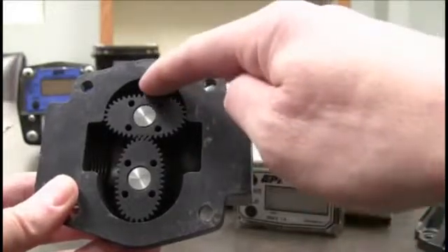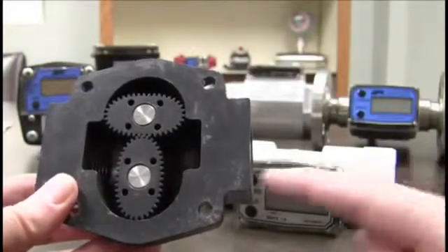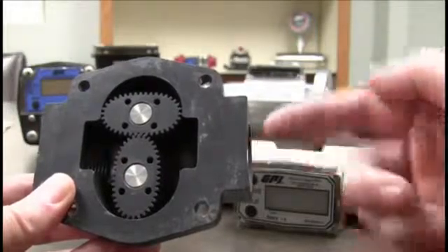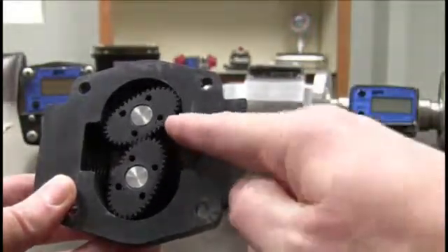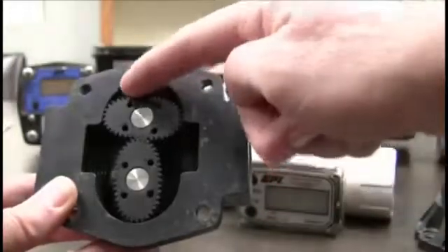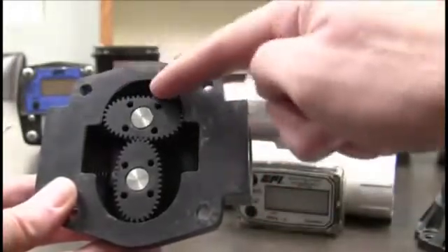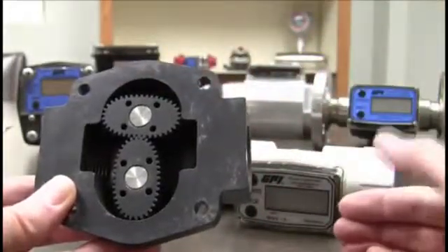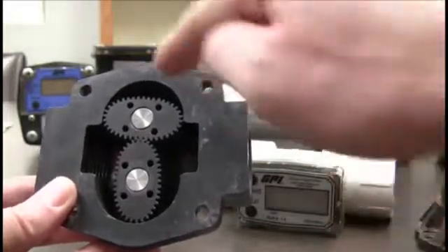And you see this little chamber here. That is where the fluid goes through. So if you have your fluid coming in this way, it's going to come in through here. And you get a little chamber of the fluid right there, and that chamber never changes size, so it doesn't matter if it's thick like oil or thin like water, that chamber always holds the exact same amount of fluid.